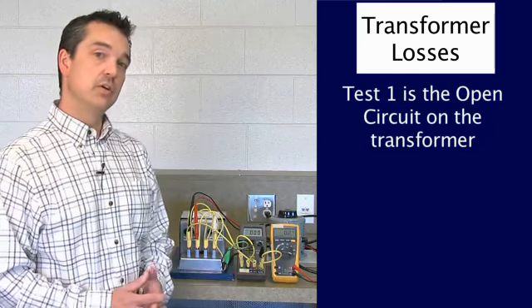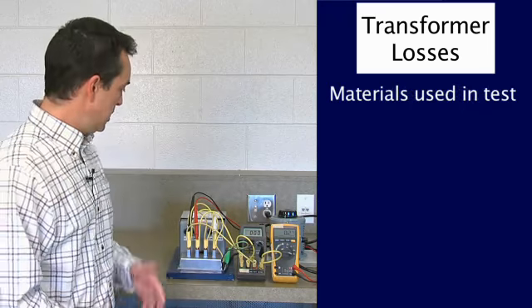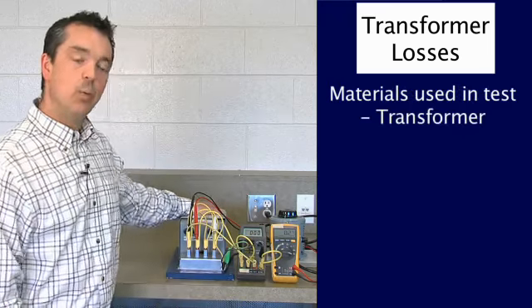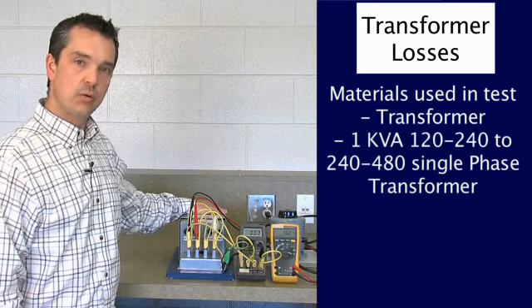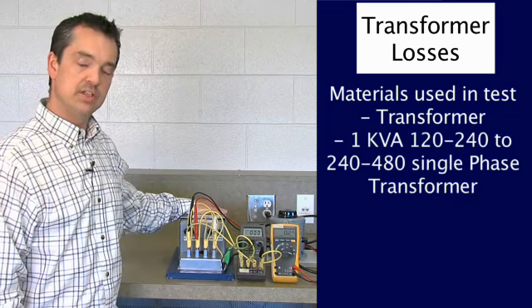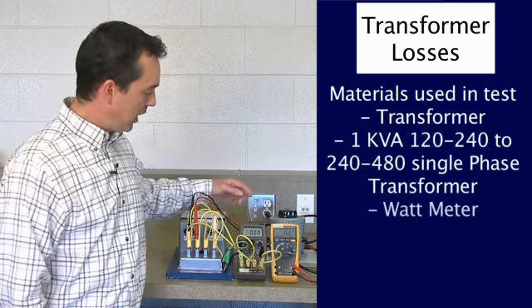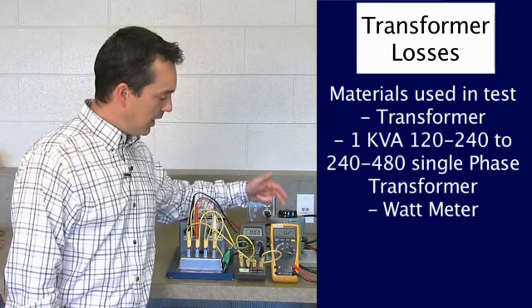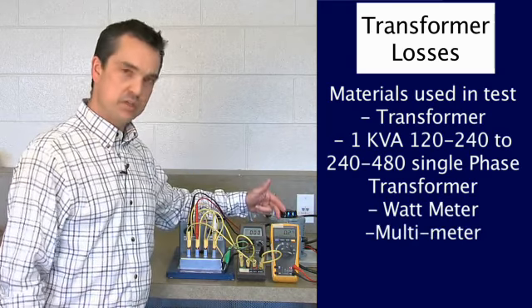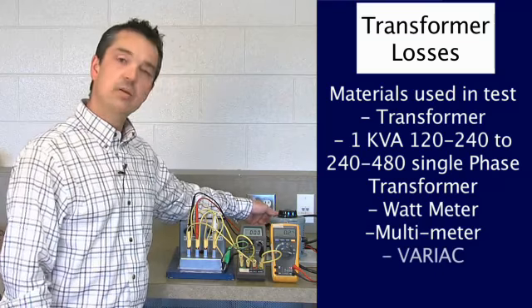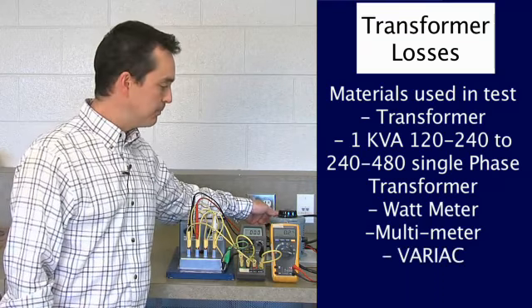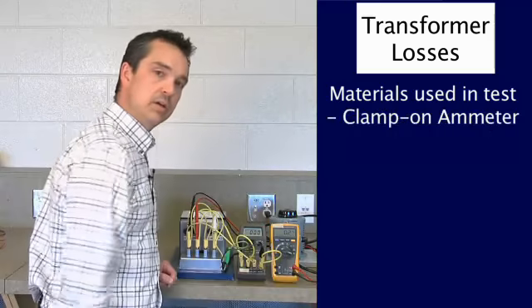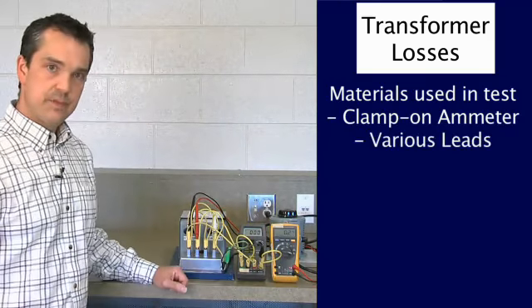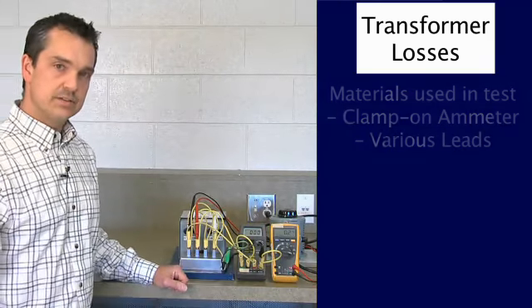Before I do that, let's take a look at the material necessary to do this. I have a transformer, a 1 kVA, 120/240 to 240/480 single phase transformer. I have a watt meter. I have a multimeter that I'm going to use for voltage measurements. I have a variable AC supply, or a variac, and I have a clamp-on ammeter, as well as various leads. That's what's necessary to do the entire test.